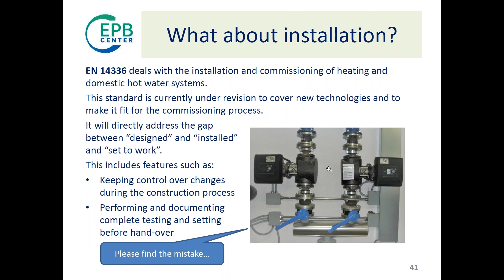Here's an example, try to find the mistakes. This is an installation checked some days ago: you see a perfect electronic pump, and they are throttling with electronic pumps. Just because nobody noticed a setting, the pump was running with a head of 24 meters when only 6 was needed. As a chain reaction, this high head caused pressure that opened valves and overheated rooms. So a simple bad commissioning, where they forgot to input the parameters in the pump, resulted in a disaster for energy performance.